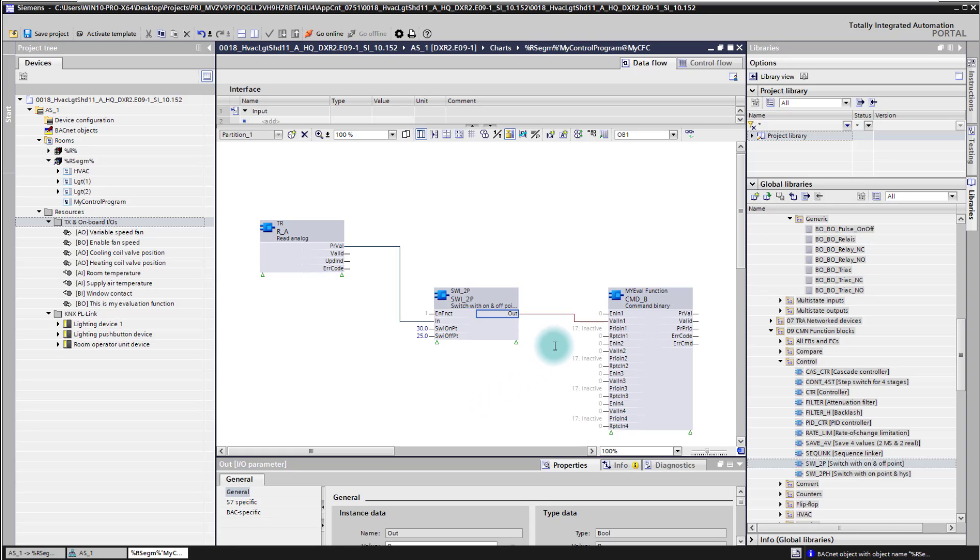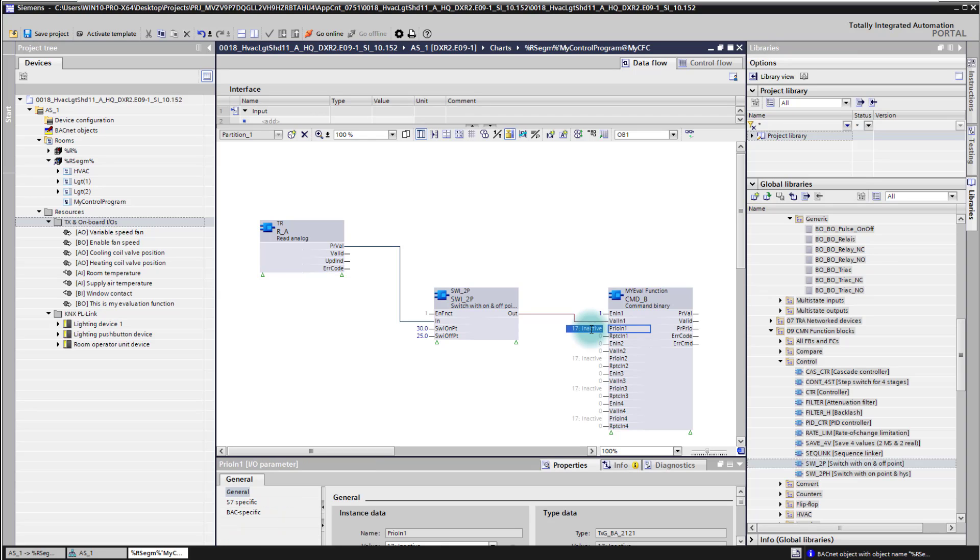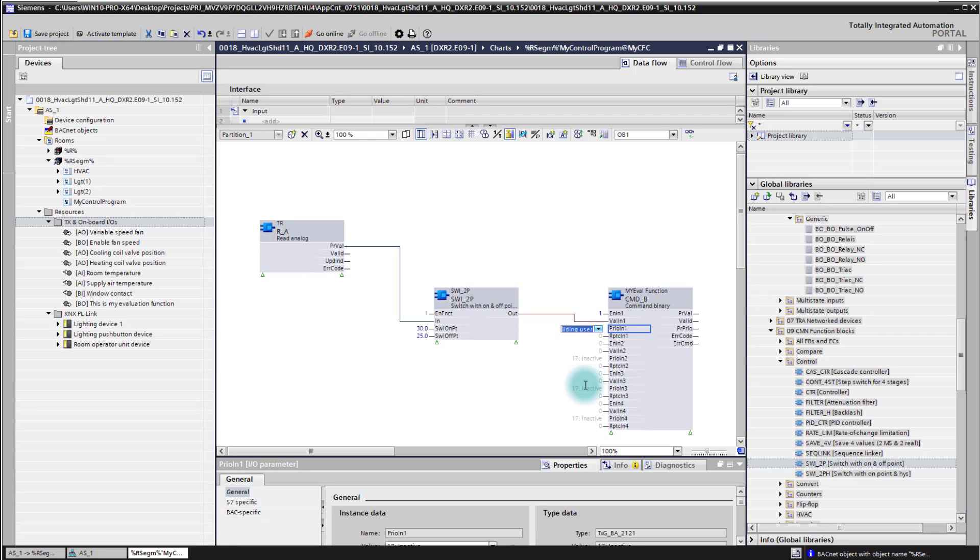So here in our simple example we have just one. We need to enable the output of course. And then also here give it a priority at this priority. That is the BACnet priority which I can choose now. And we use here priority 13 manual operation for this example.